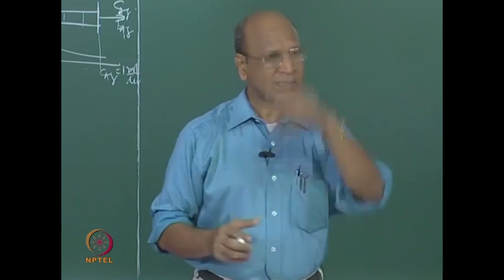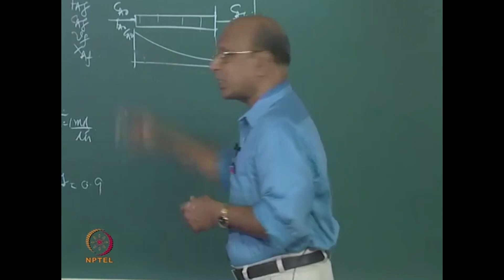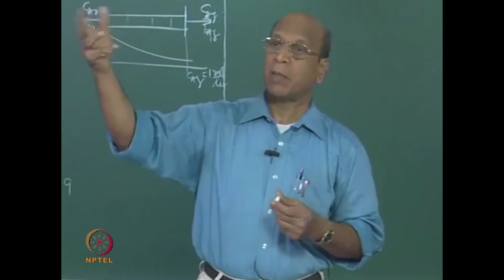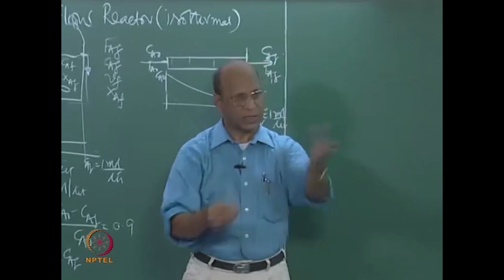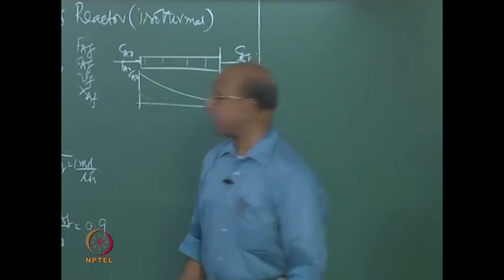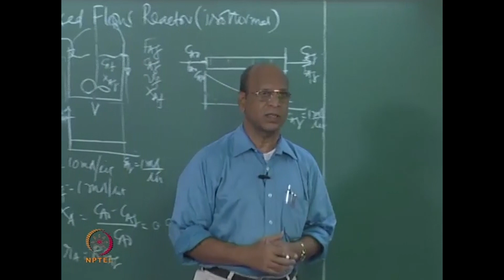If the reaction is highly exothermic, simply putting an external jacket may not give me that kind of area where I can control the temperature. Highly exothermic, I want to control around maybe 75 degrees, but with only that jacket and whatever coolant is available, I may still be getting around 90. What do I do? So people take out a stream, put an external heat exchanger, and again send it back. That is one way. The other way is to directly put coils inside. There are many ways.